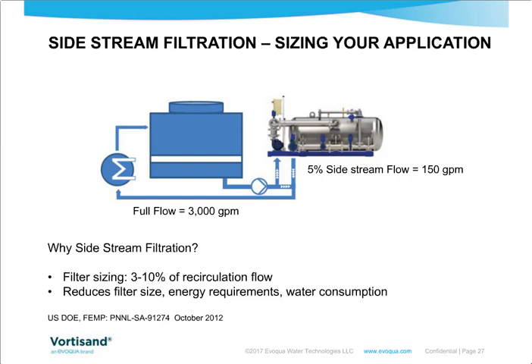Side stream removal allows you to reduce your filter size and your pump size, so your energy requirements are drastically lower. And the water consumption, how much water you need for backwashing, is also drastically improved.